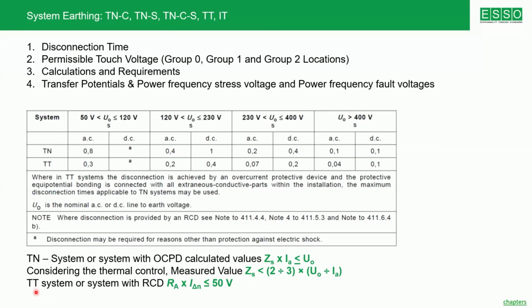And if you are going for a TT system, or if you are using a system for fault protection, you are using an RCD, then there is another type of calculation available. The fourth subject to be considered is transfer potential and power frequency stress voltage and power frequency fault voltage.